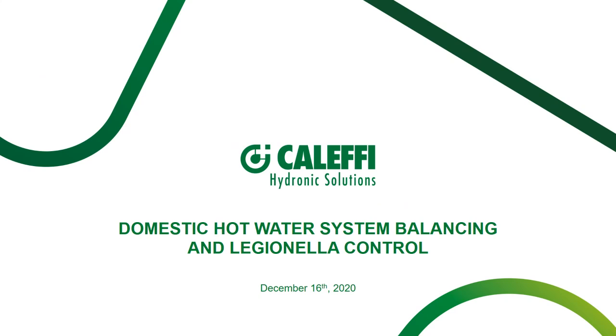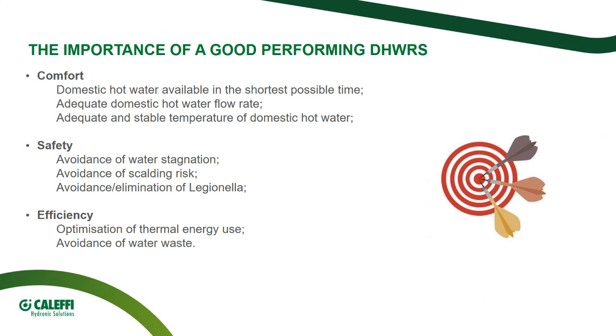Yeah. Okay, so today we will spend almost 1 hour together speaking about domestic hot water system balancing with particular attention to Legionella control. In other words, we have to evaluate what is the importance of a good performing domestic hot water recirculation system. So in order to start, let's remind together what are the targets that in design phase we have to consider and take into account in order to have a good performing, efficient domestic hot water recirculation system. First of all, some of them are related to the comfort of the user. I mean, the domestic hot water shall be available to the user in the shortest possible time. There are also some standards for that. The hot water and cold water flow rate shall always be adequate, so I never have to miss availability of water.